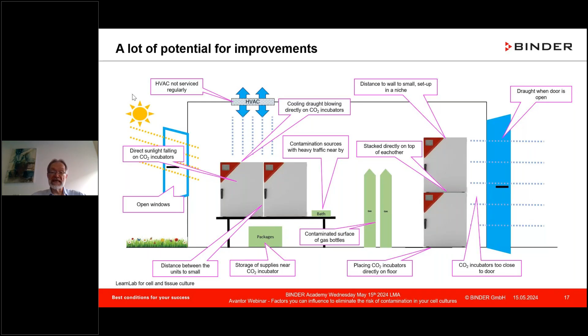And as with the sunlight, ladies and gentlemen, never ever place a CO2 incubator directly below an HVAC system. You have cooler air blowing on top of the surface, there you have condensation taking place inside of the incubator, and that is not good for good growth. It only supports contamination, the spreading of contamination.